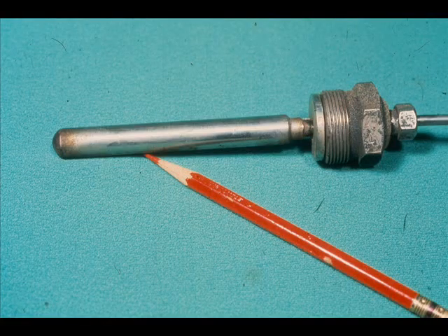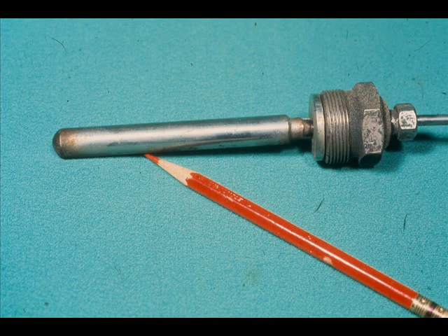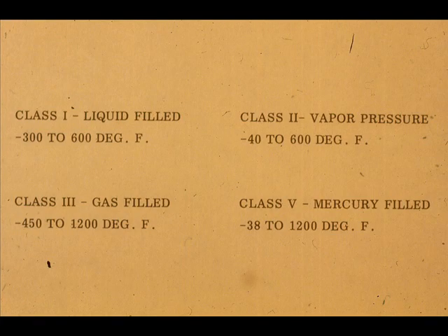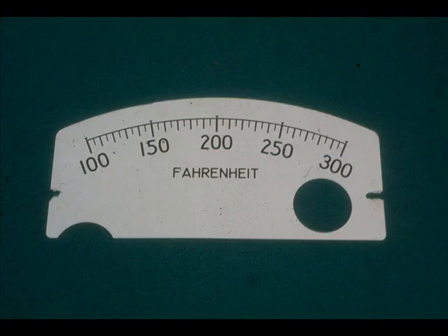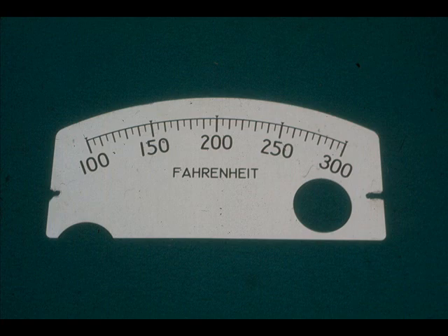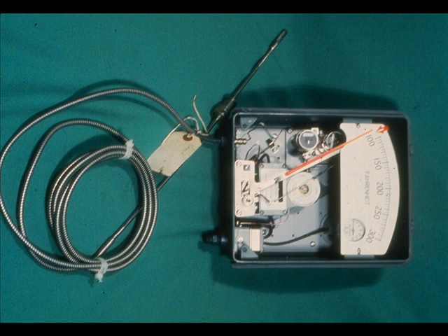Some disadvantages of the filled systems are the bulb may be too large to fit the available space. The maximum temperatures are not as high as electrical temperature measuring systems. Also, the span of the filled systems cannot be as narrow. Usually, the entire system has to be replaced if the tubing is broken or any part of the system fails.